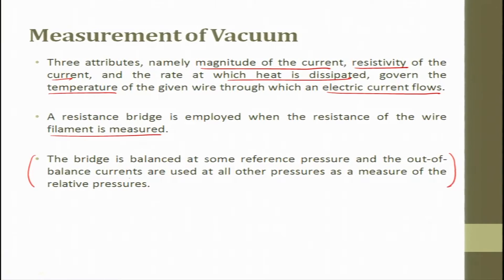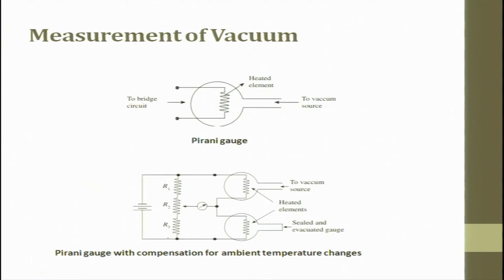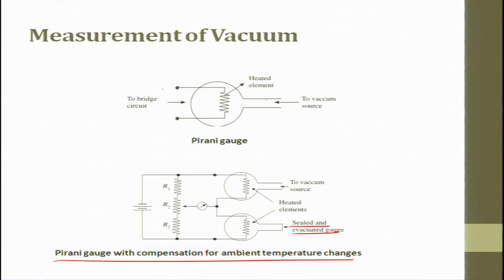The bridge is balanced at some reference pressure and the out-of-balance currents are used at all other pressures as the measurement of relative pressures. In a Pirani gauge, a vacuum source is there, a bridge circuit is there, and this is the filament which is heated. You apply constant heat and try to measure the voltage. The Pirani gauge with compensation for ambient temperature change has a heated element whose output is attached to a voltmeter and then to another heated element in a sealed evacuated gauge with resistance and applied voltage.